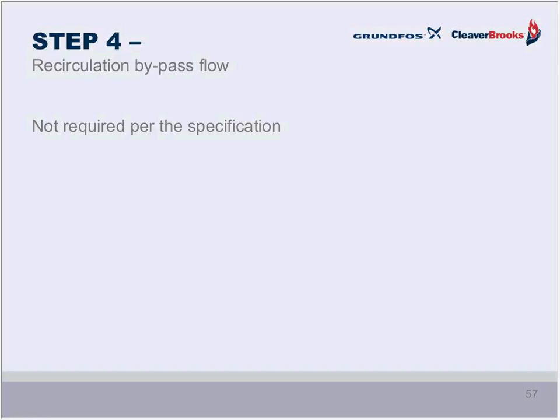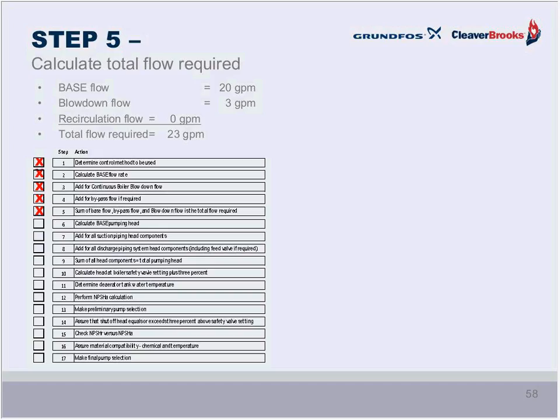Next, we have to calculate the total flow, and we simply take the base flow of 20 plus the blowdown flow of 3. There are 0 gallons per minute of recirc required, so our total flow is 23. Do you remember on the previous exercise we had 28 gallons per minute? So right off the bat we're saving water, and really that equates to saving energy. And that 28 gallons was required in both previous exercises for the other control modes. Okay, so we can proceed to the next step.